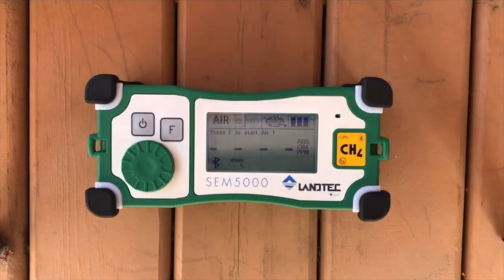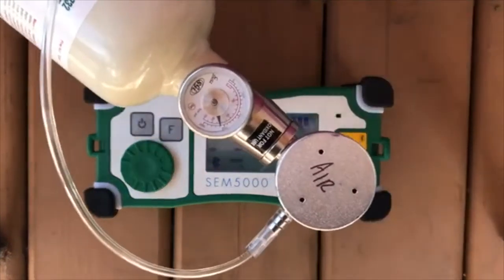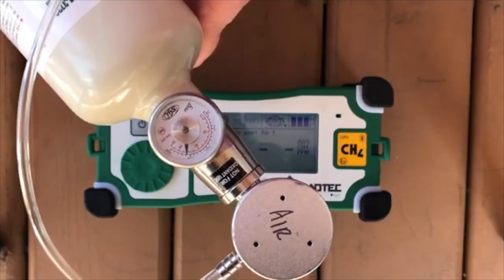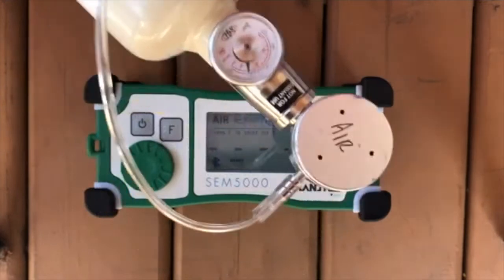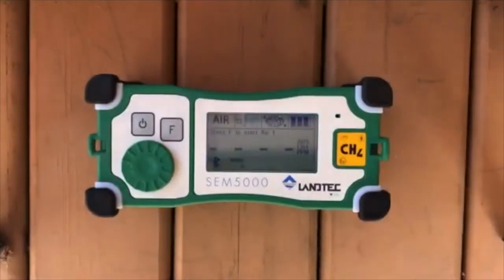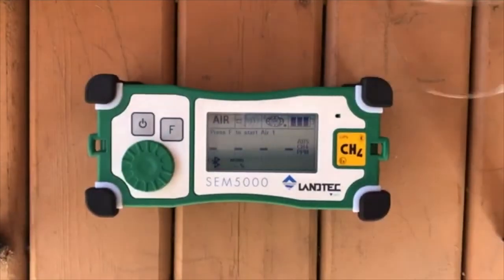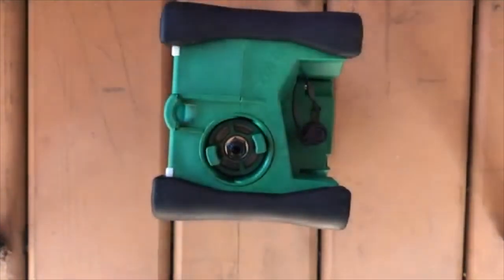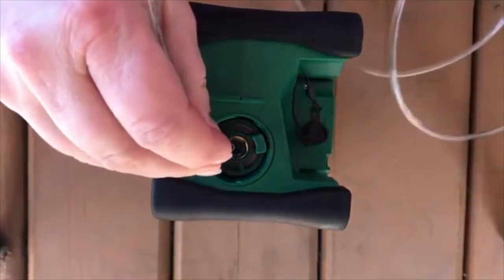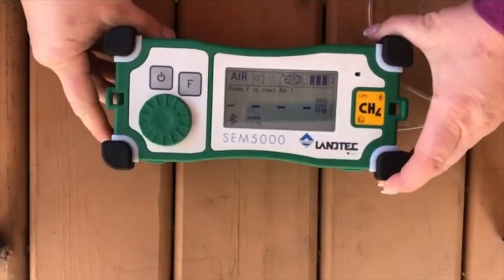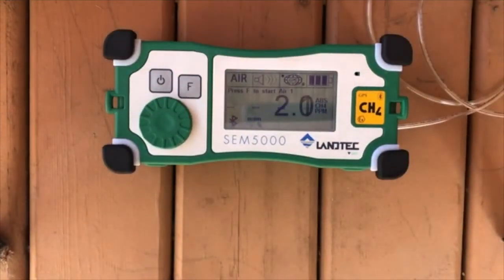And at this point you would then get your calibration gas, your air gas. If you were lucky enough, or if you purchased 2 regulators, you would want to have 1 regulator on each of the air and the gas. It makes it a lot easier than switching back and forth, as you need to bump test 3 times with each gas and air. So first we connect the air. This is simply through the use of the push to connect port on the side. Make sure you push all the way in. It's fully connected. And then press F to start the test.